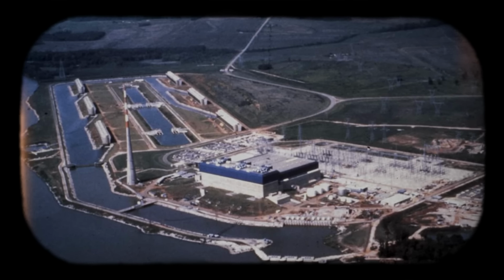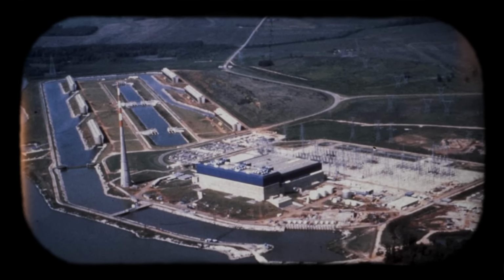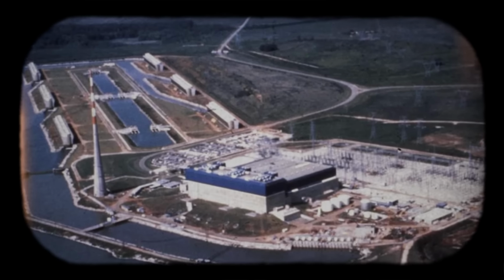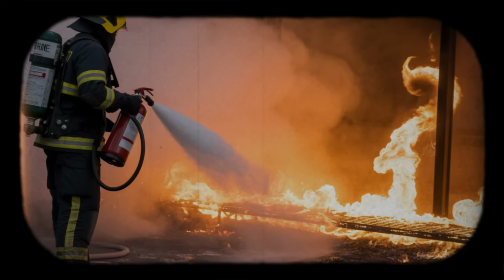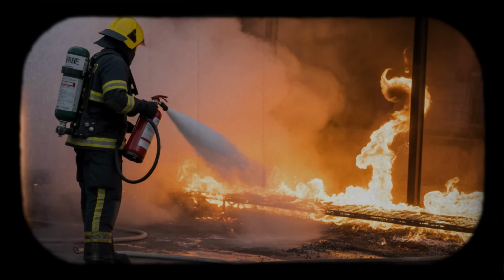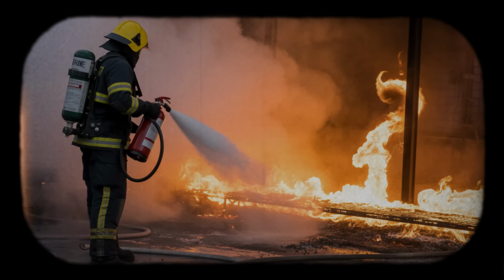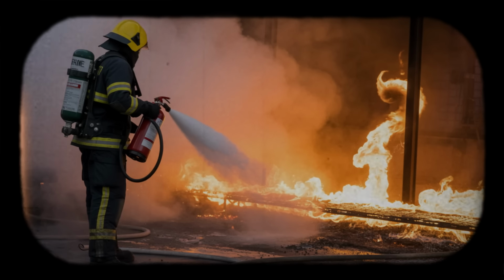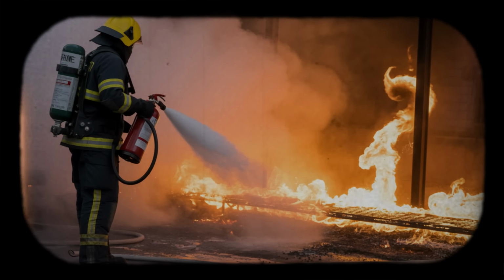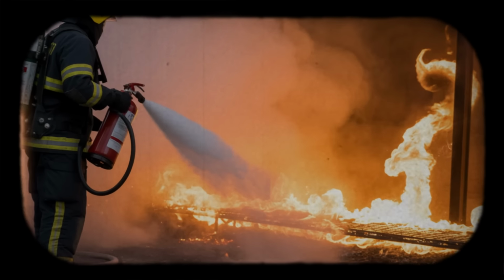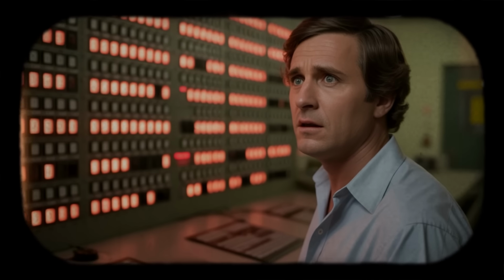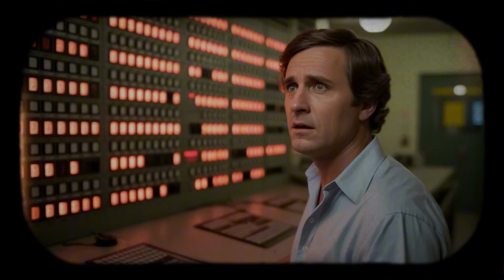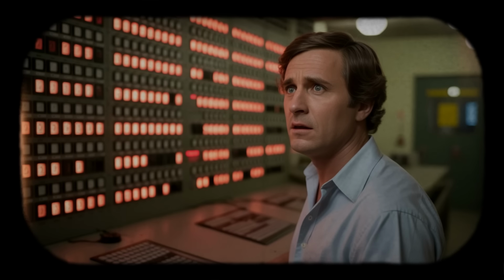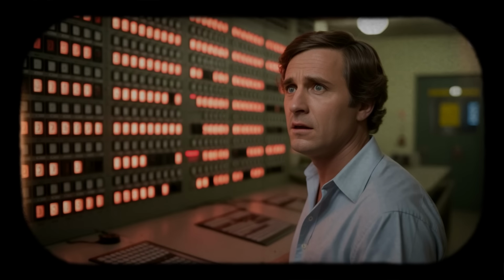Ventilation systems maintain air pressure differentials to prevent radioactive contamination from escaping the reactor building. Dampers open and close automatically based on pressure sensors and radiation monitors. Control signals for these dampers travel through the same cable trays affected by the fire. Intermittent shorts produce spurious signals that mimic abnormal conditions. A damper might appear to be closing when it is actually open. A radiation monitor might show a false alarm. Operators must now question every instrument reading. Which signals are real? Which are artifacts of circuit damage? The distinction is not always clear.